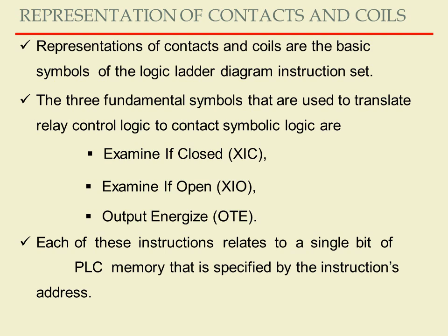The three fundamental symbols that are used to translate relay control logic to contact symbolic logic are XIC, examine if closed, XIO, examine if open, and OTE, output energize. Each of these instructions relates to a single bit of PLC memory that is specified by the instruction's address. So this instruction will relate to a bit in the PLC memory. Let us see how.